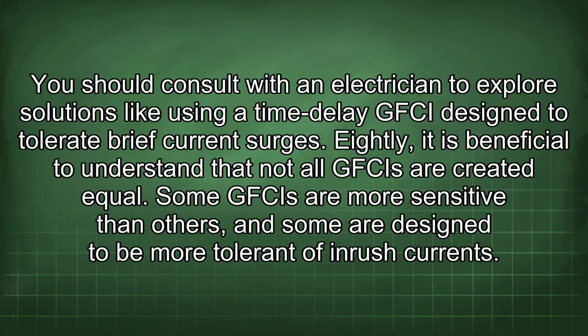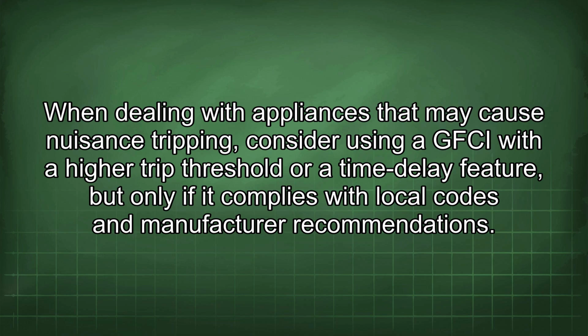You should consult with an electrician to explore solutions like using a time delay GFCI designed to tolerate brief current surges. 8. It is beneficial to understand that not all GFCIs are created equal. Some GFCIs are more sensitive than others, and some are designed to be more tolerant of inrush currents. When dealing with appliances that may cause nuisance tripping, consider using a GFCI with a higher trip threshold or a time delay feature, but only if it complies with local codes and manufacturer recommendations.